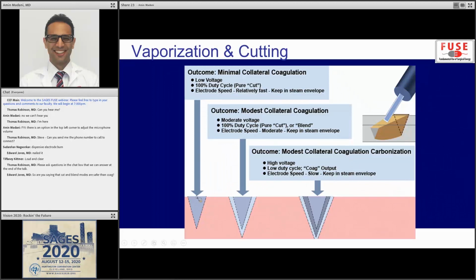So let's take this example on the left here. I apply a cut function, so it's low voltage, low thermal energy. I apply it here. I raise the temperature of the cells above 100 degrees Celsius, so this is going to vaporize. It's going to cut it, literally. But the cells around it are not going to experience a very high rise in temperature. It's going to bring it to the 60 to 90 degrees zone, enough to cause desiccation, but not enough to cut it. But because it's low voltage, the surrounding collateral effect is very minimal. So you're just going to see a lot of vaporization. You won't see too much desiccation or coagulation.